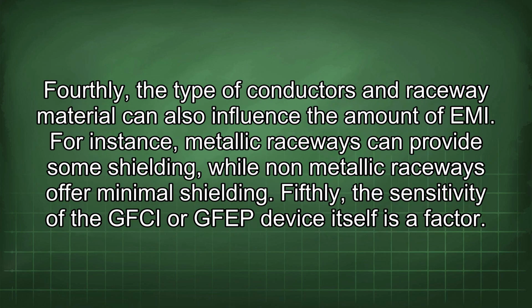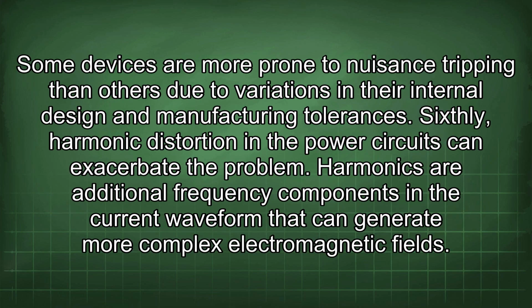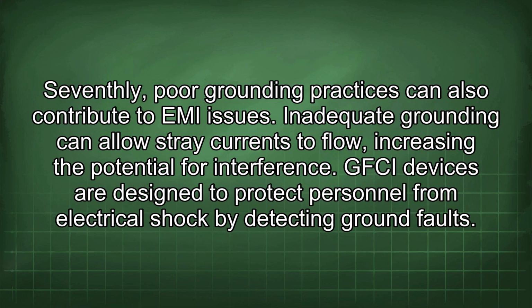Fourthly, the type of conductors and raceway material can also influence the amount of EMI. For instance, metallic raceways can provide some shielding, while non-metallic raceways offer minimal shielding. Fifthly, the sensitivity of the GFCI or GFEP device itself is a factor. Some devices are more prone to nuisance tripping than others due to variations in their internal design and manufacturing tolerances. Sixthly, harmonic distortion in the power circuits can exacerbate the problem. Harmonics are additional frequency components in the current waveform that can generate more complex electromagnetic fields. Seventhly, poor grounding practices can also contribute to EMI issues. Inadequate grounding can allow stray currents to flow, increasing the potential for interference.